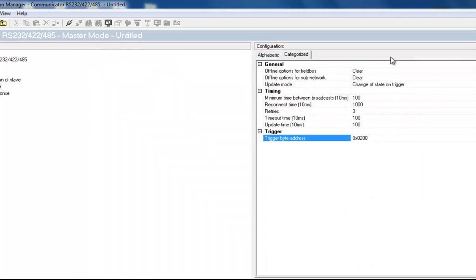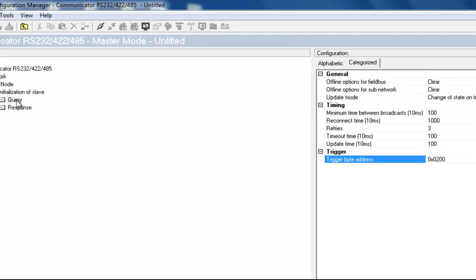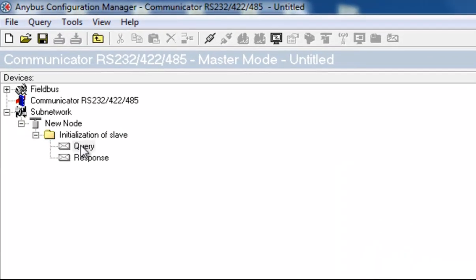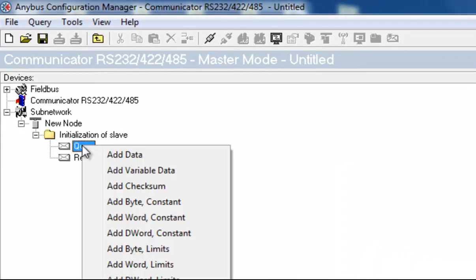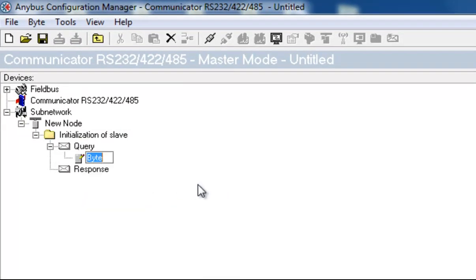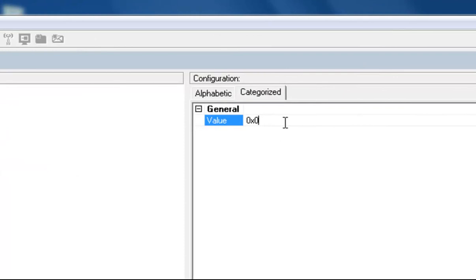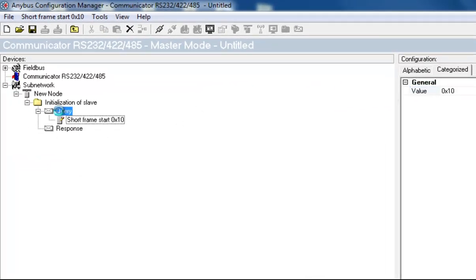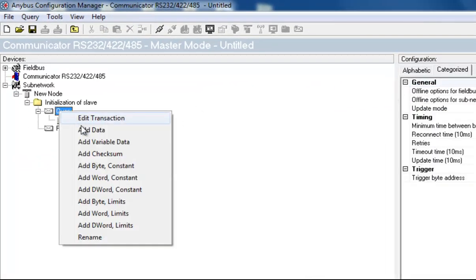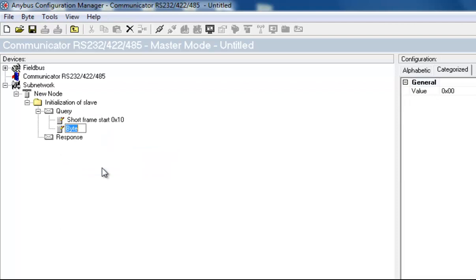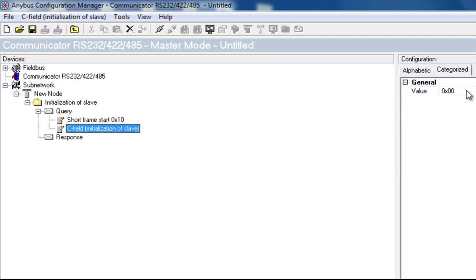I then create the telegram itself, which is to initiate the slave. We add a byte and call this Short Frame Start Byte, with a hexadecimal value of 10. I also set the value to 10. I insert a byte, which is the C field for the MBUS telegram. I set this to 40, which is the value for the command Initialization of Slave.